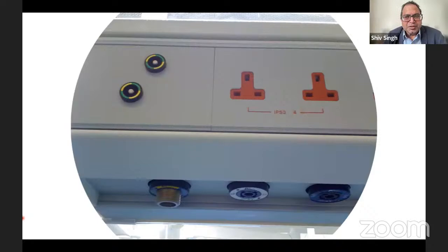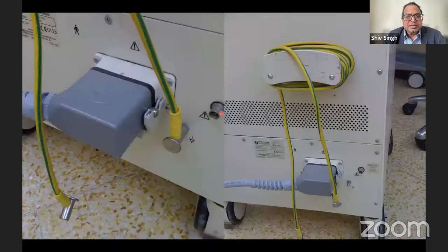This is the one where the machine and the equipotential points will be connected. So this is the equipotential wire. You can see that it's connected on the machine at the point, so that's the equipotential wire. And you can see the equipotential points here. That's the equipotential point that's connected. And the other bit goes on to the pendant, the equipotential point on the pendant. So that's how this is there.